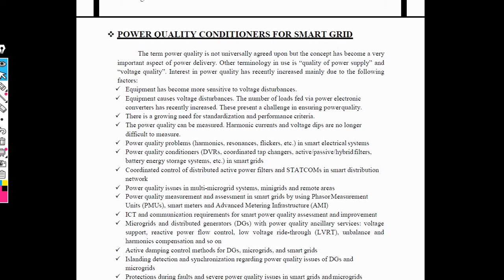Then there are different power quality problems in the smart grid like harmonics, resonance, and flicker. These are the several problems that occur in the smart electrical grid system. At that instant we need a power quality conditioner, and also require a tap changer, and the study of active and passive filters and hybrid filters. Also maintain the power quality in the battery energy storage system in the smart grid. These are the several parameters that will be controlled in the smart grid.